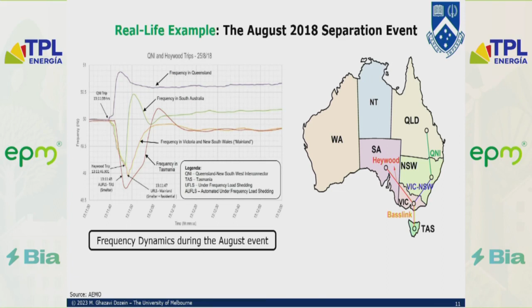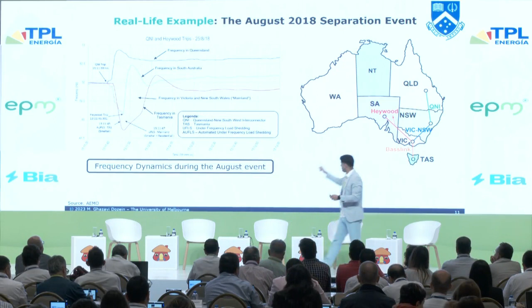The green curve showed that South Australia faced under-frequency and then over-frequency following its separation. During this event, we had two system separations, one gigawatt of load shedding because of very low frequency conditions, and 200 megawatts of PV tripping. One event caused a lot of events to happen right after it — a chain of events.